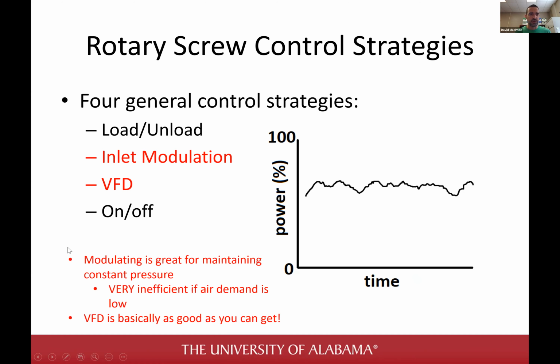So I've got some more notes down here. As I said, modulating is great for maintaining constant pressure. One thing I didn't mention is that it's very inefficient if the air demand is low. You can imagine if the air demand is very low, you still have this motor running as loaded as it can, but you're closing the valve. And so the motor and the screws are really just fighting against that inlet valve, and not really fighting against system pressure.